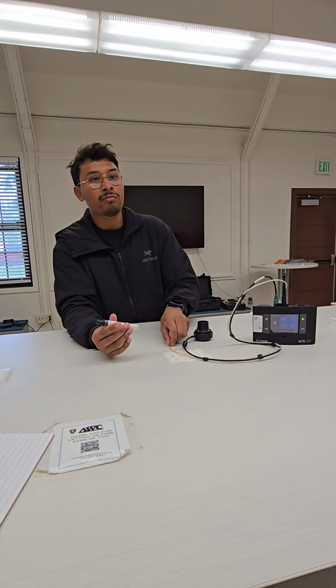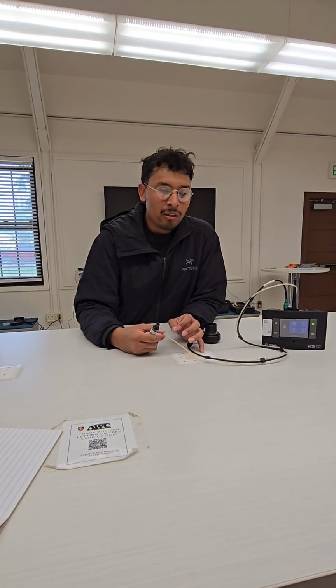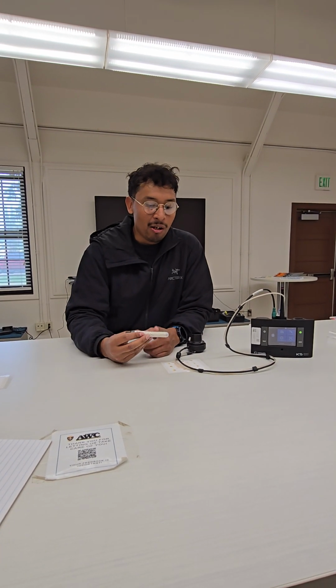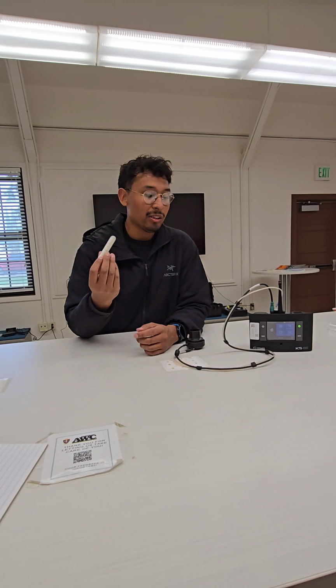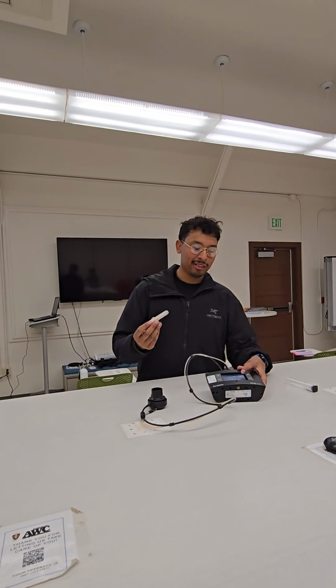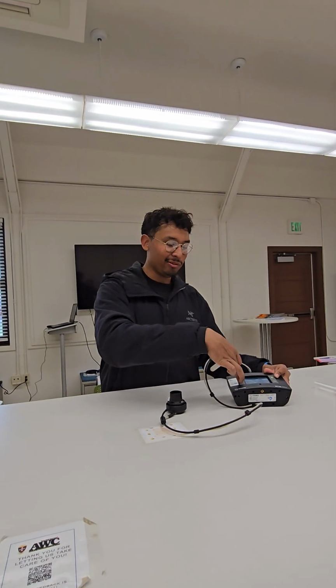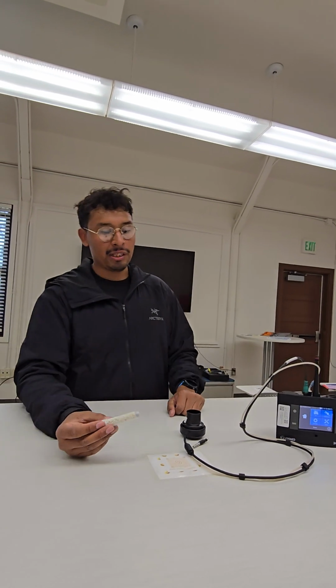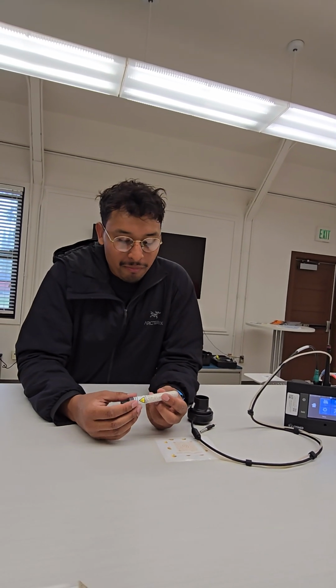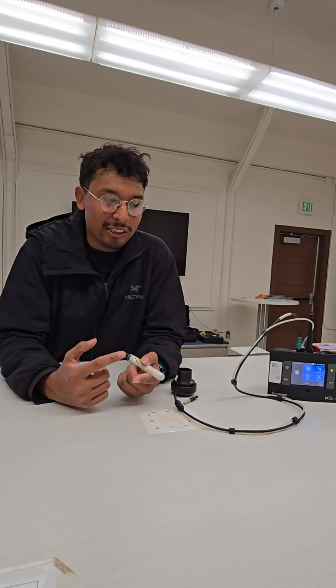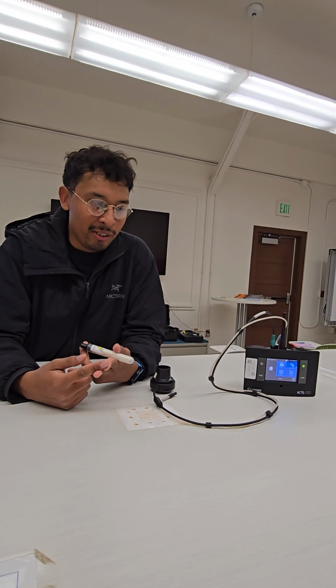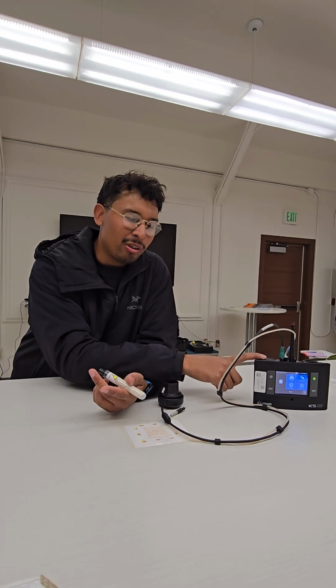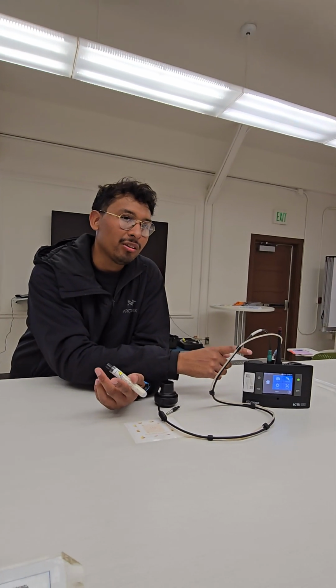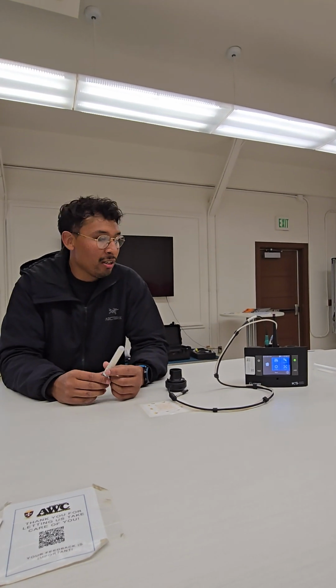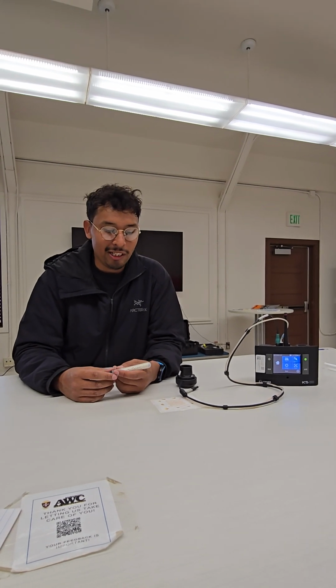That's really it. Is that based off use or just calibrate your 365? Once again, this one is a lot with environment. So if you want to store these same as the sampling line, somewhere dark, cool, that could help a lot with it. But yeah, this one is more environment as well. So sampling line, CO2 scrubber, and environment. O2 analyzer is more time, so that one's just about a year no matter what. And then the gas tank should last a few years unless you end up leaking it accidentally.